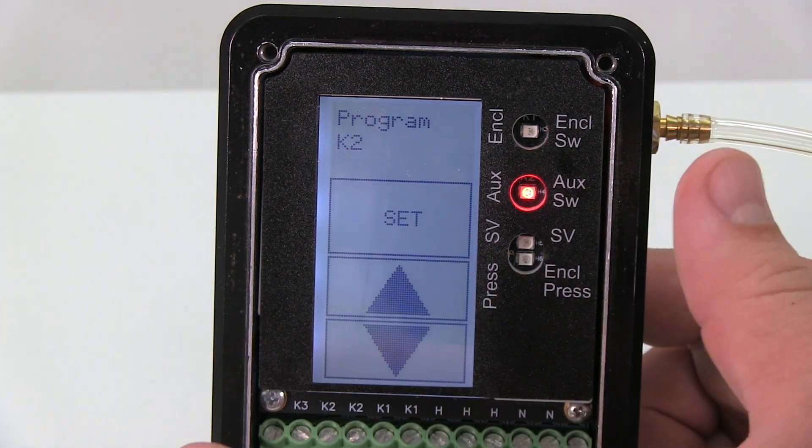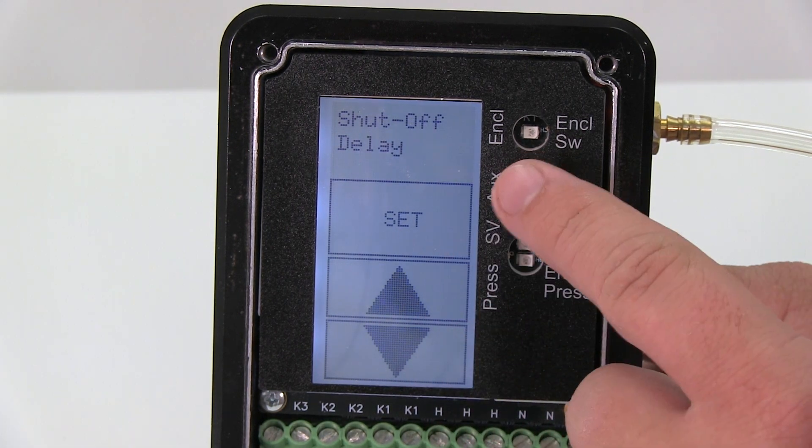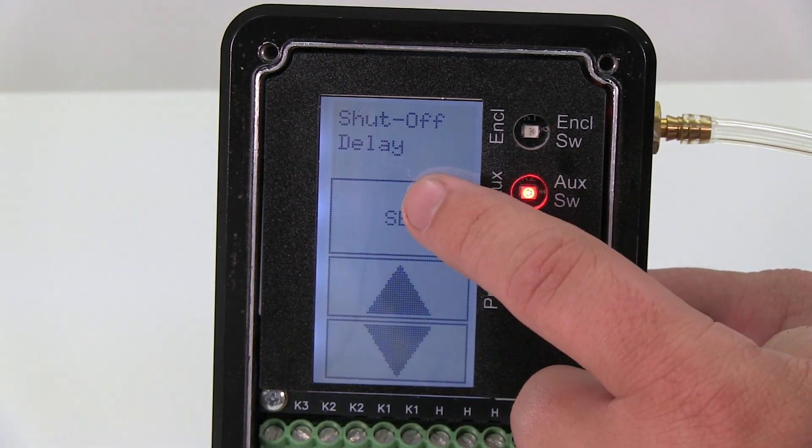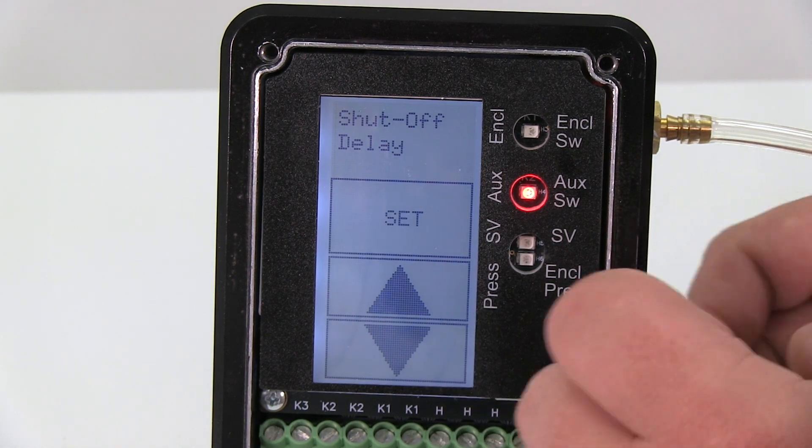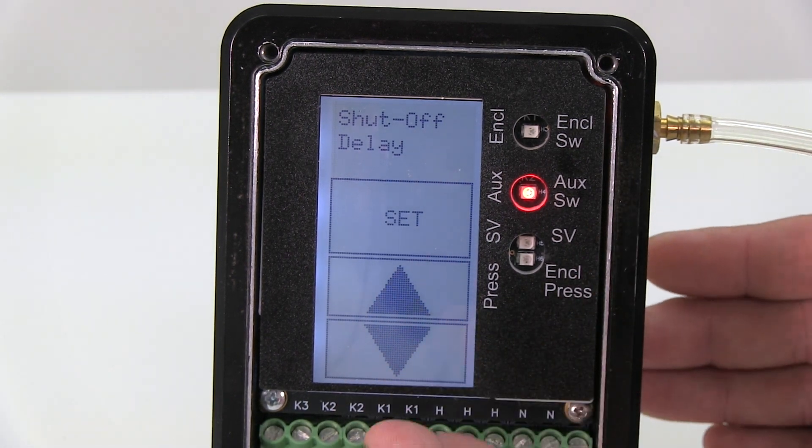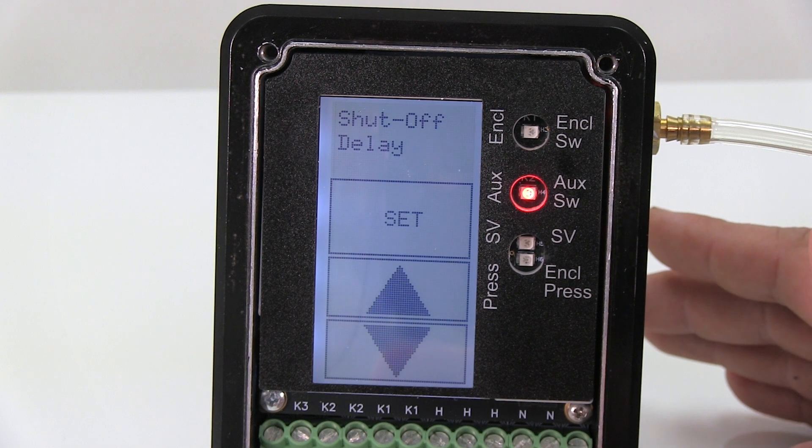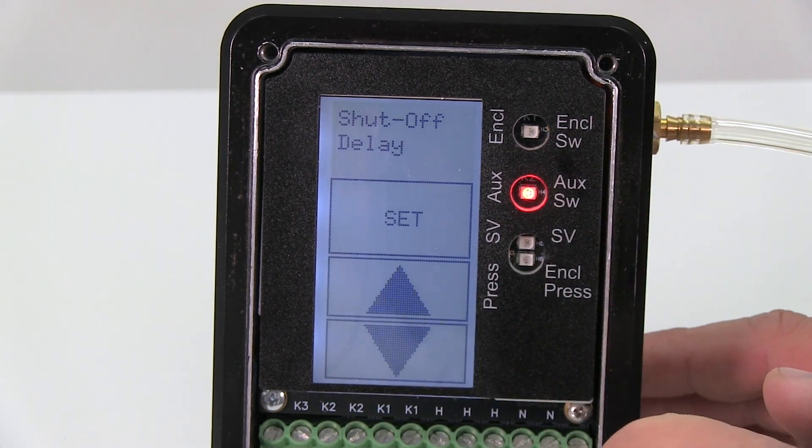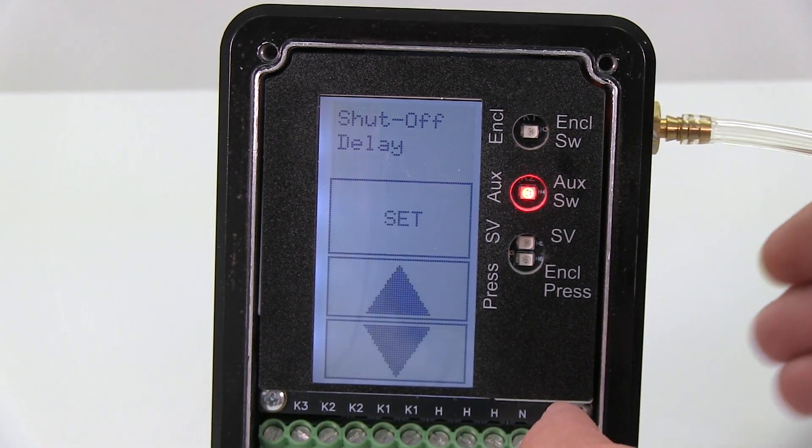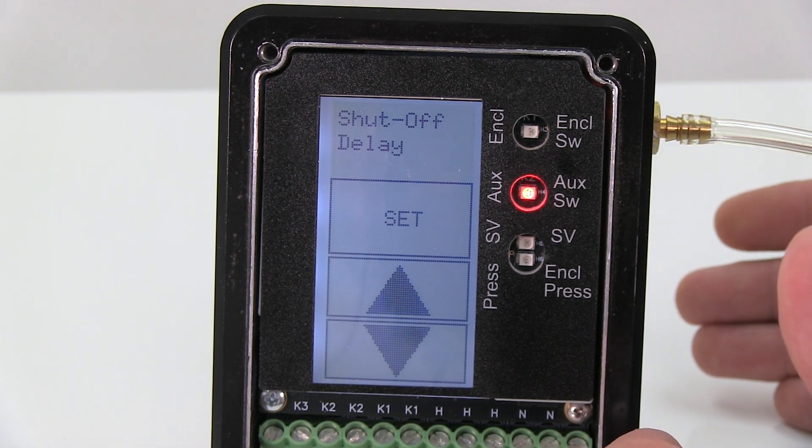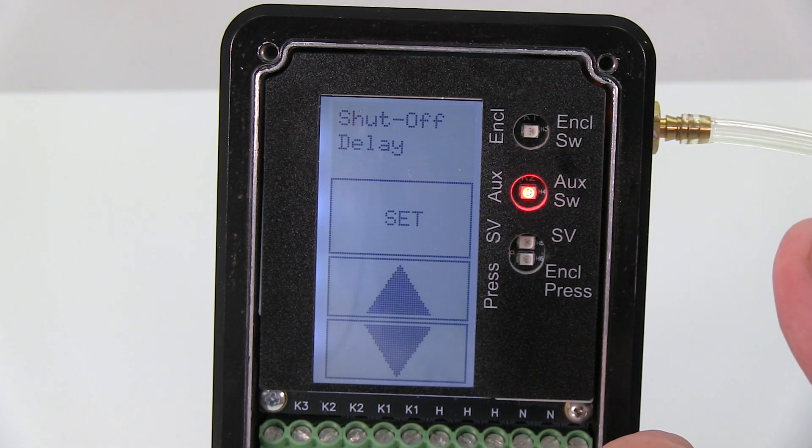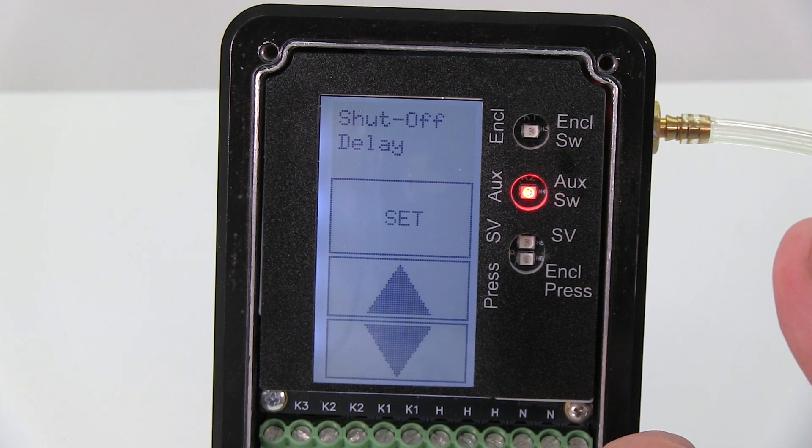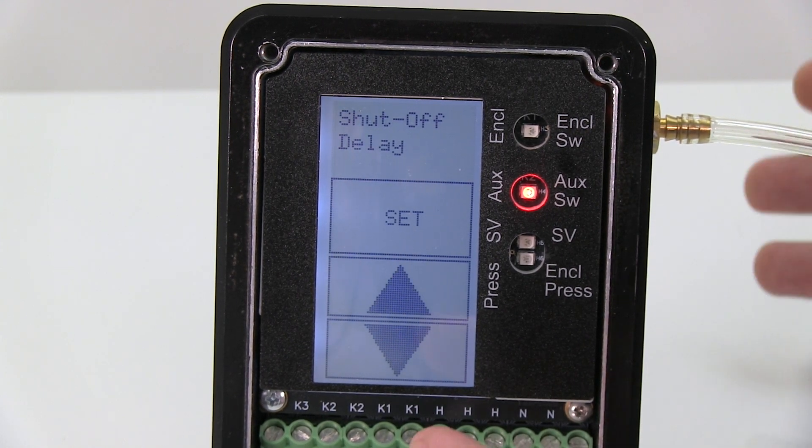The next menu item is shutoff delay. So if I lose positive pressure, one of the preset programs will kill power to my enclosure. Now the shutoff delay - what this does is once I lose positive pressure, you can put a 30-second delay on that. The shutoff delay timer starts. After that 30 seconds is up, then it'll kill power to my enclosure. It just gives you a little delay before shutting down power to your enclosure.